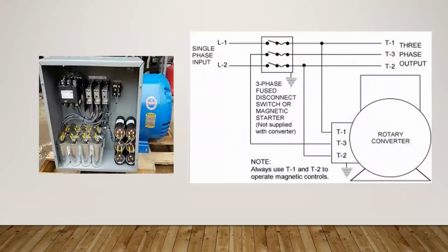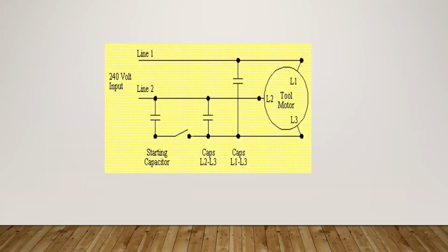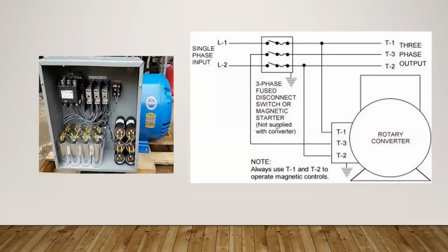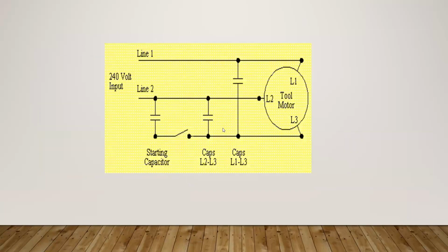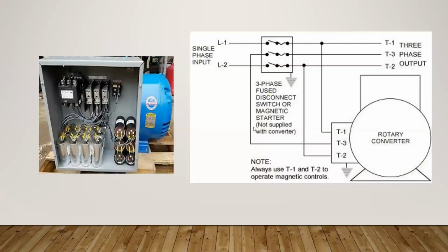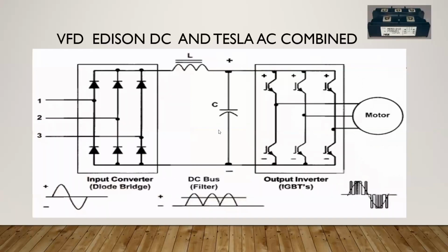So literally, instead of taking the static type, where we're just using phase shift capacitors to get it up and running, with the phase angles between them, you really need to derate this motor by about 25% that you're running off of. With a rotary phase converter, the same thing. You probably get by with a 15% deration in some cases, but you really need to look at that load. And you've got extra capacitors and things in there that are options.